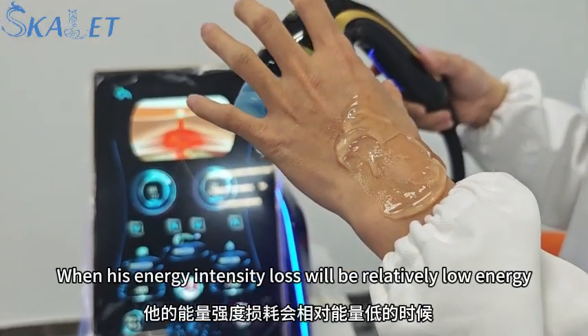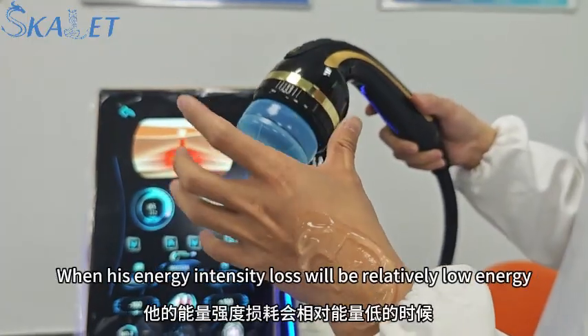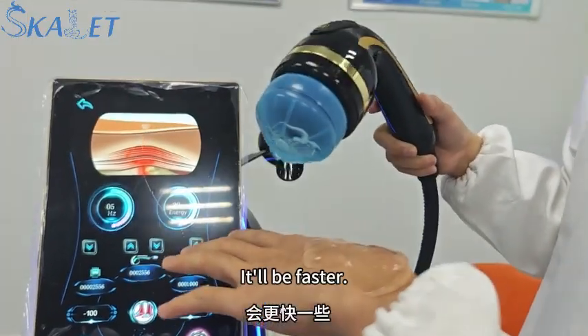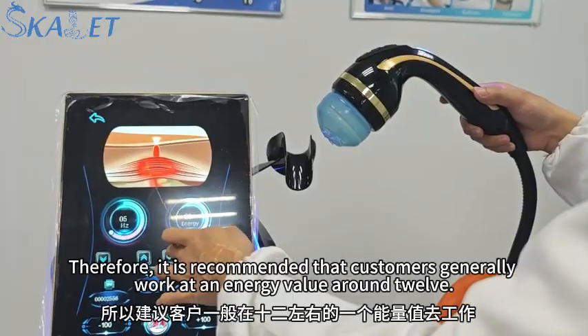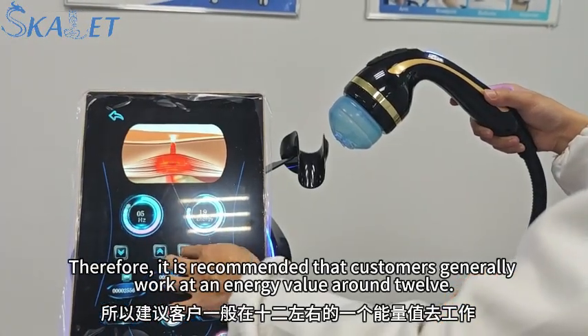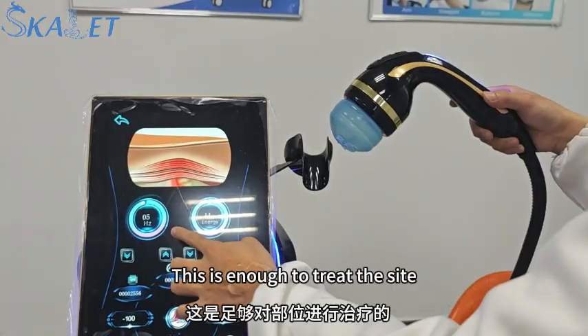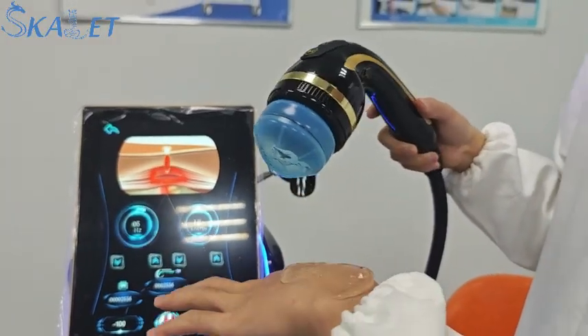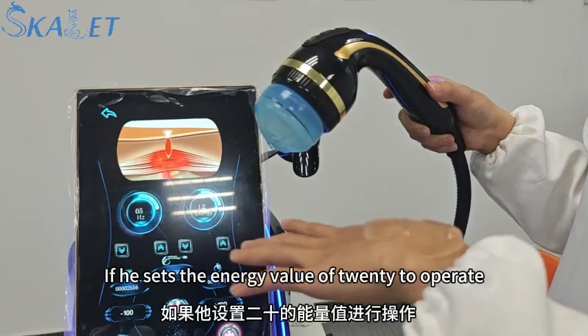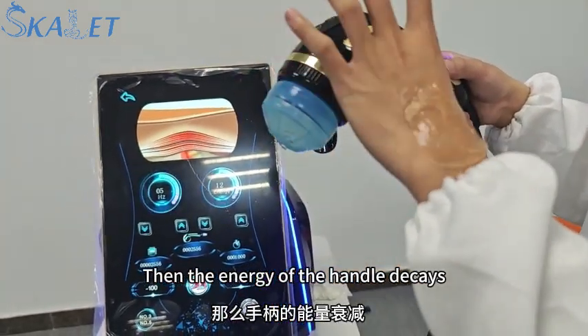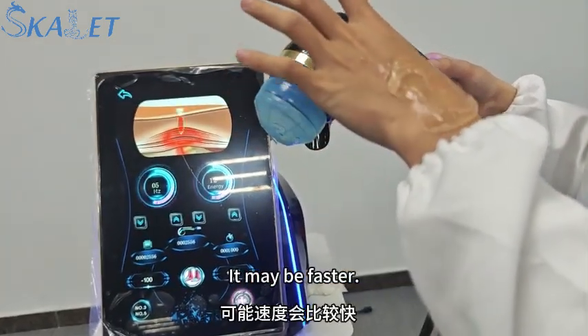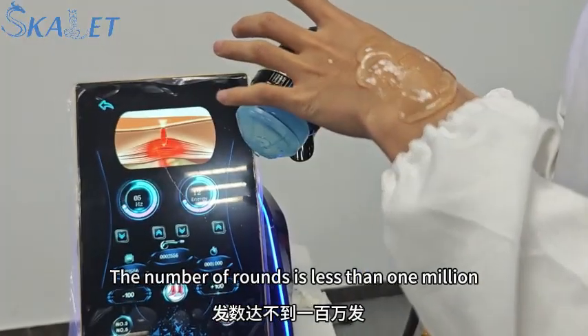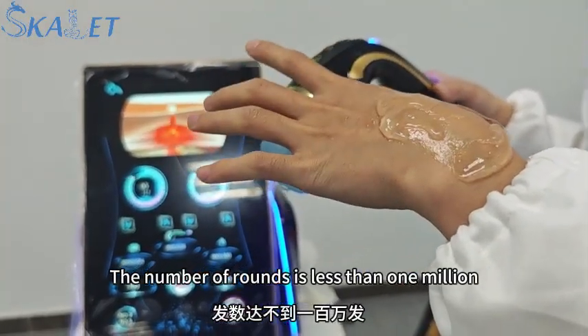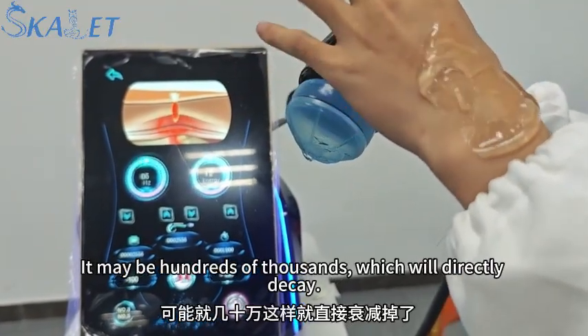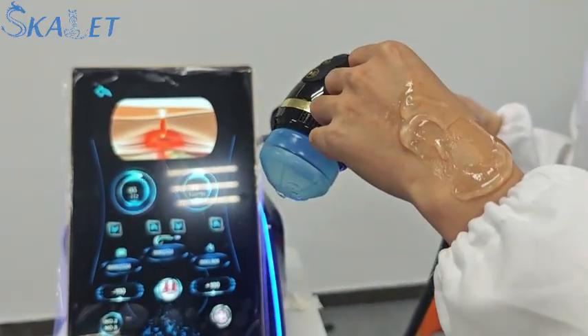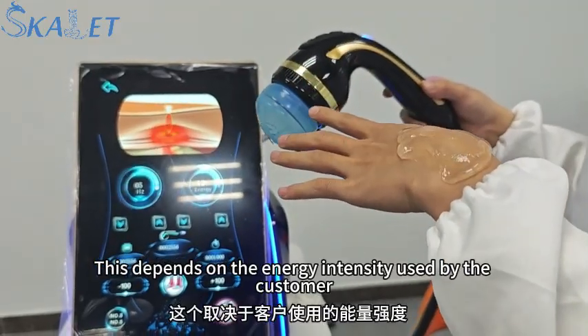After a long time at the highest energy, the handle's energy intensity loss will be faster. Therefore, it is recommended that customers generally work at an energy value around 12. This is enough to treat the site. If he sets the energy value of 20 to operate, then the energy of the handle may decay faster. The number of rounds is less than 1 million. It may be hundreds of thousands, which will directly decay. Then you may need a new handle. This depends on the energy intensity used by the customer.